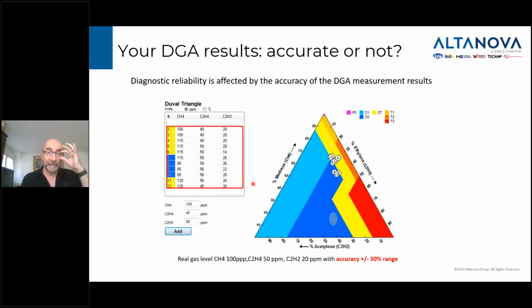Here's another example, visually, of what will happen if you move from a low accuracy system to a high accuracy system. Here we have the optimal measurement of the different gases, methane, ethylene, and acetylene. And we use a system that has an accuracy of plus or minus 30%. When we plug them into the Duval triangle, you can see that some of the diagnostics tell you that you have a D2. Many of them tell you that you have a DT, and potentially you're very close to a D1. So potentially with a 30% accuracy system, the same sample can give you 3 different types of diagnostic.